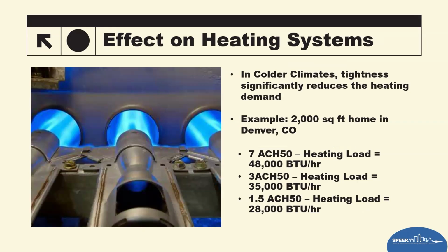Now, in Texas and Oklahoma, we're both predominantly a cooling climate. We don't require a lot of heating, but we do have heating in our houses. Most people now are not going to just not put heating in. But since that happens and we use split systems that use the same air handler, this can become more of a challenge, because the heating can be grossly oversized since we need the fan speed and CFM for cooling. And then, of course, the newer systems will have a dip switch or a tap that slows it down for heating so it doesn't have the same blast of air when it's hot.